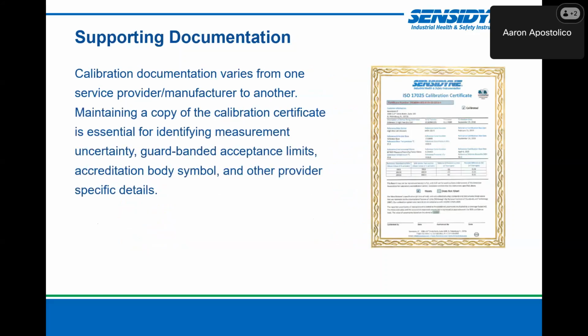Now, calibration documentation varies from one service provider or manufacturer to another. Maintaining a copy of the calibration certificate is usually an essential part of that for identifying measurement uncertainty, guard-banded acceptance limits, accreditation bodies, and other provider-specific details.